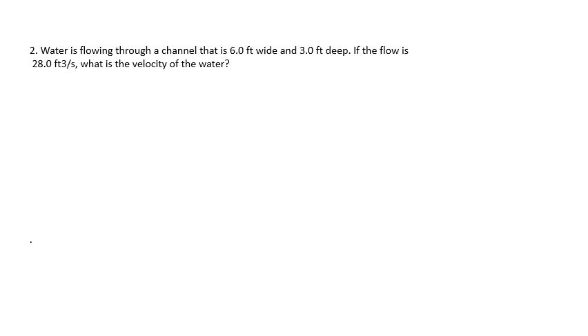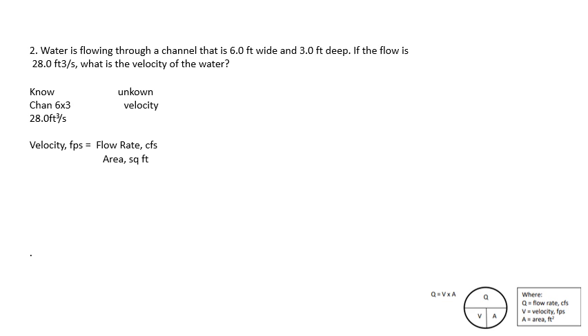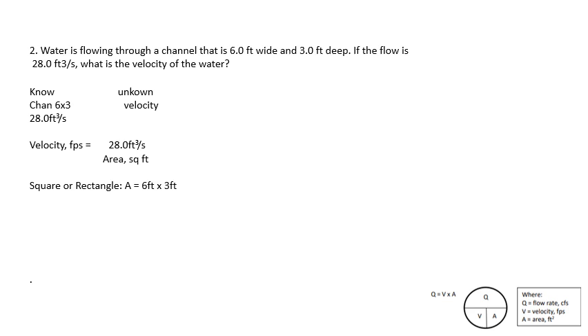Question number two: Water is flowing through a channel that is six feet wide and three feet deep. If the flow is 28 cubic feet per second, what is the velocity of the water? We know the channel is 6 by 3 feet and the flow is 28 cubic feet per second. Velocity equals flow rate divided by area. Area of a rectangle is length times width: 6 times 3 equals 18 square feet. Plug that in and the answer is 1.55 feet per second.